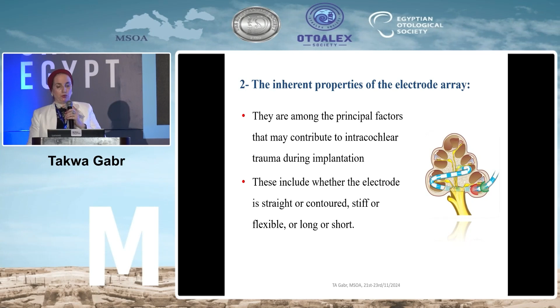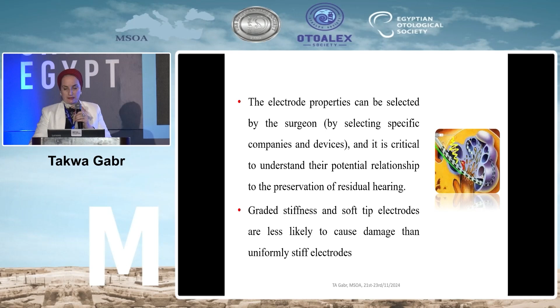Other factors are related to the inherent properties of the electrode array, such as their types, whether straight or contoured, stiff or flexible, long or short. Of course, selection of the electrode array is related to the surgeon, but in general, graded stiffness and soft tip electrodes are less likely to cause damage than uniformly stiff electrodes.